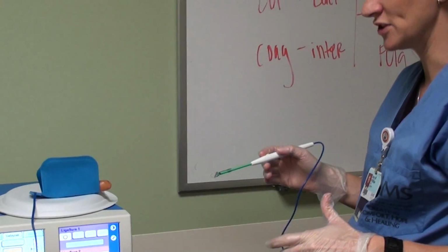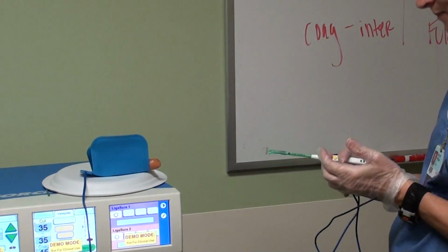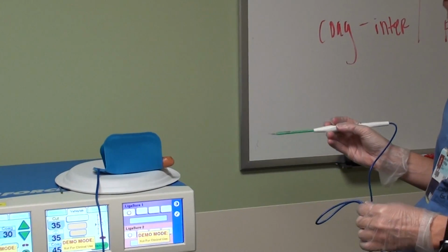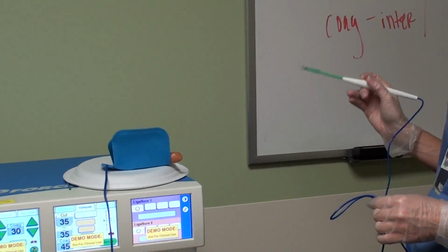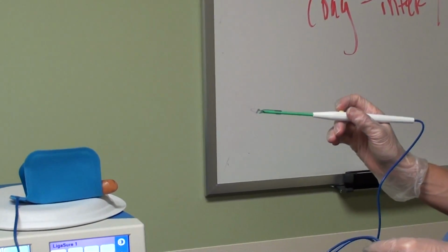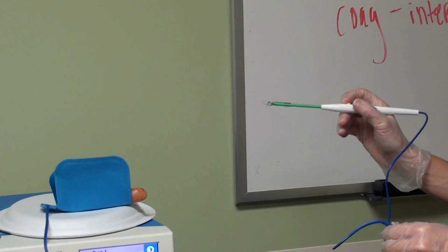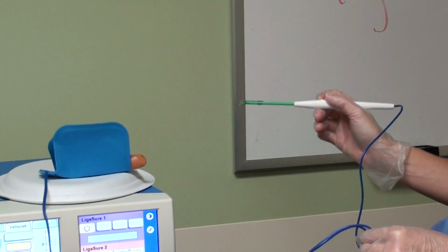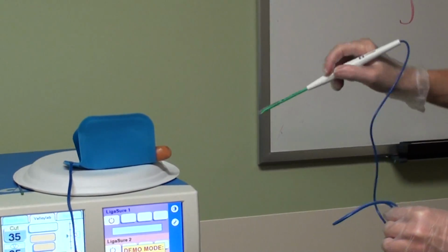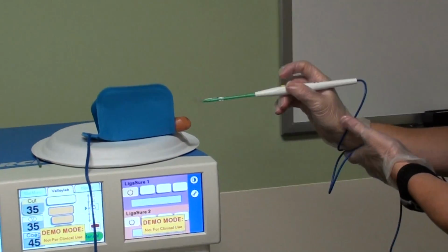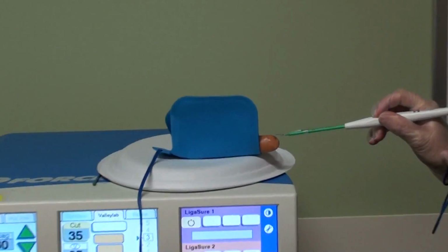So when performing a LEEP, you really want minimal thermal spread so that your pathologist can give you an appropriate read on your pathology. And so the ideal way to get your specimen is to use the vaporization technique. So again, this is achieved using the cut waveform, which is low voltage continuous, and we would use that in the non-contact technique.